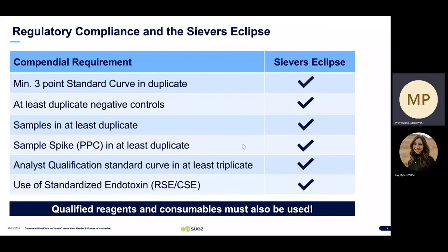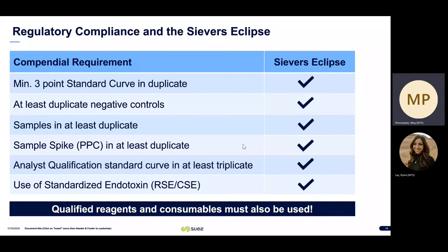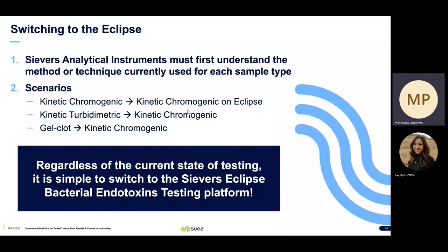Another consideration is to use qualified reagents and consumables. When switching to the Eclipse, you must first understand the method for each sample type — some samples may be tested on kinetic chromogenic and others on kinetic turbidometric. Here are some scenarios on switching: the easiest is switching from a kinetic chromogenic method to kinetic chromogenic on the Eclipse because they both utilize a microplate reader. You can also switch from kinetic turbidometric to kinetic chromogenic, or regardless of the current state of testing, it is simple to switch to the Sievers Eclipse bacterial endotoxin testing platform.